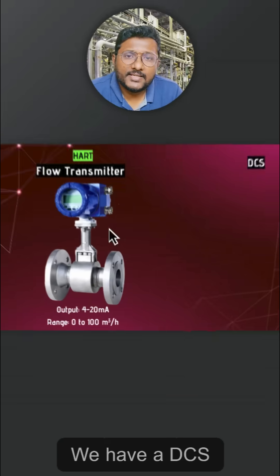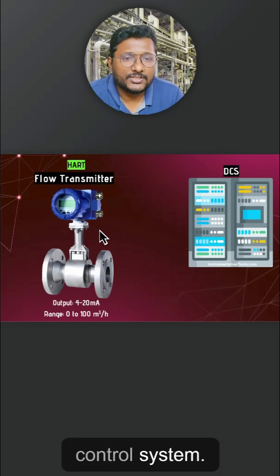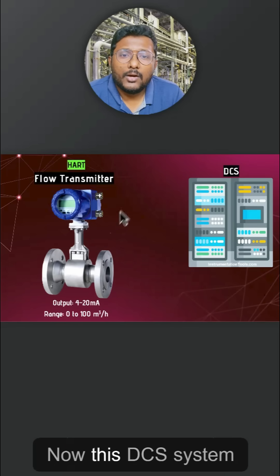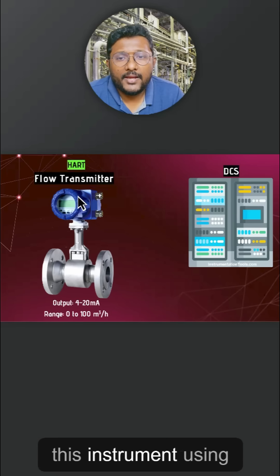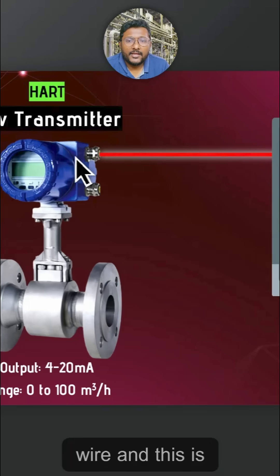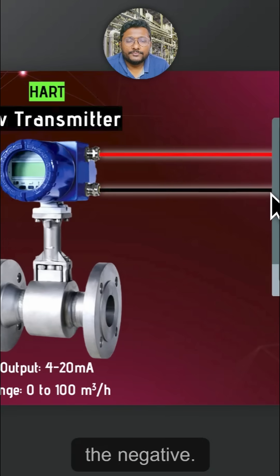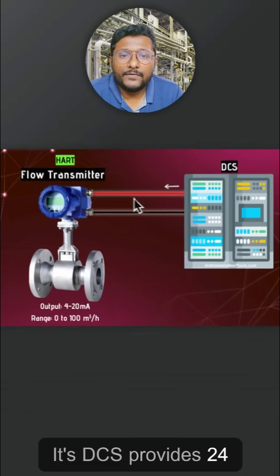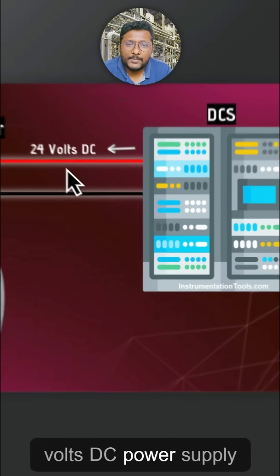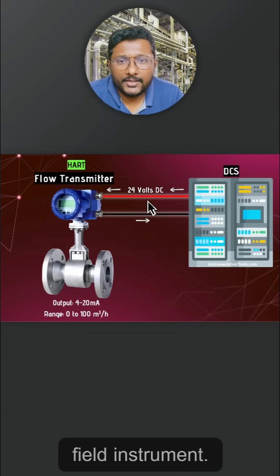We have a DCS system — a distributed control system. This DCS system is connected with the instrument using two wires: a positive wire and a negative wire. The DCS provides 24V DC power supply to the field instrument.